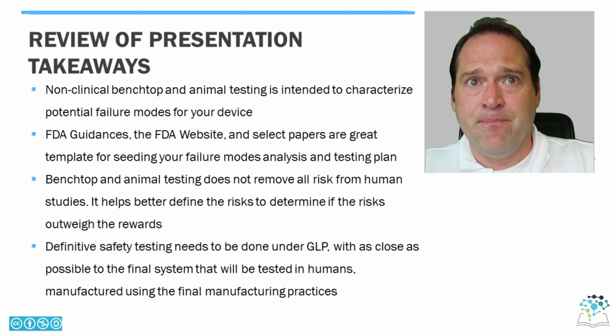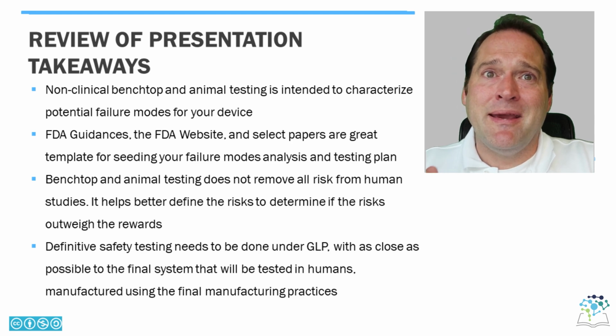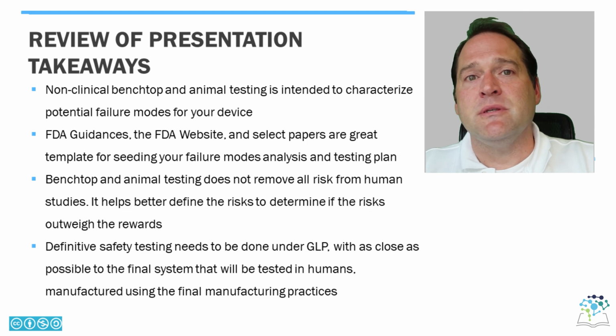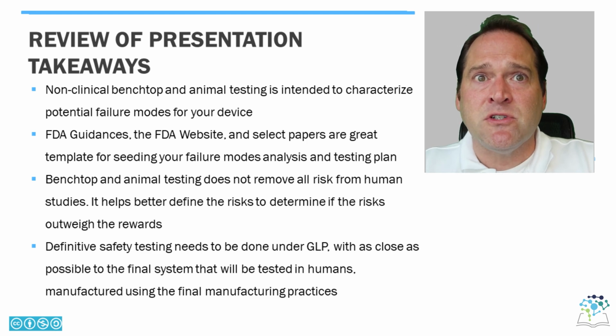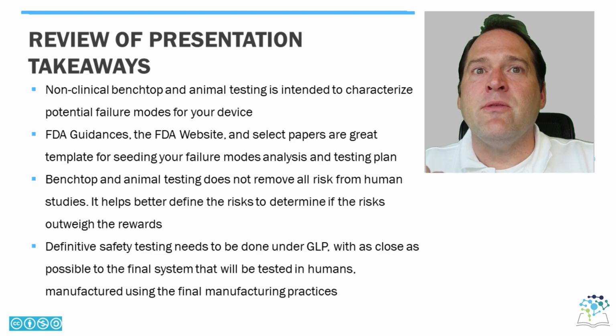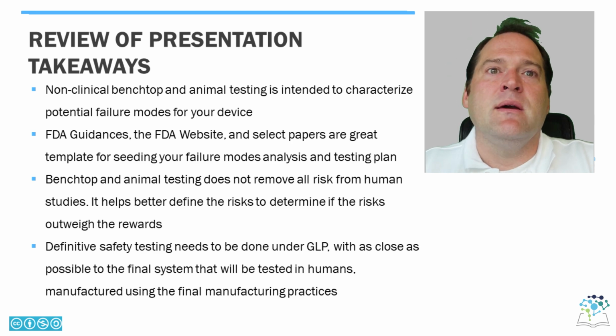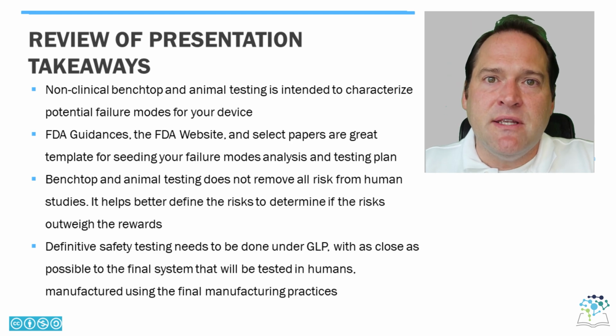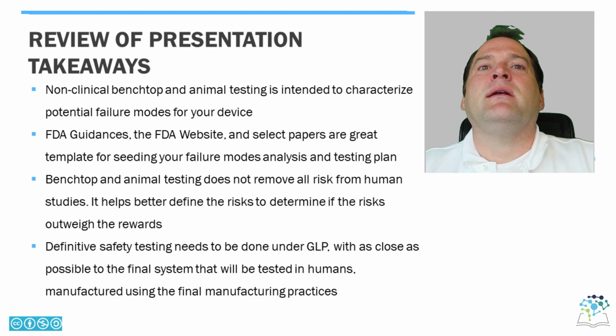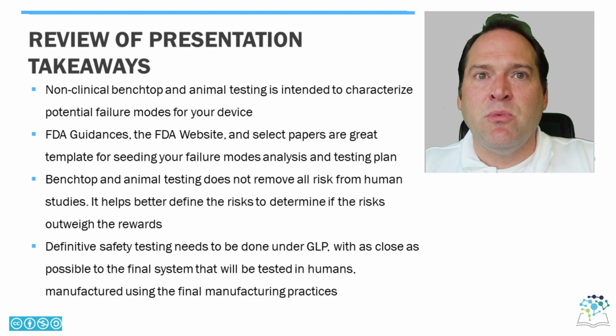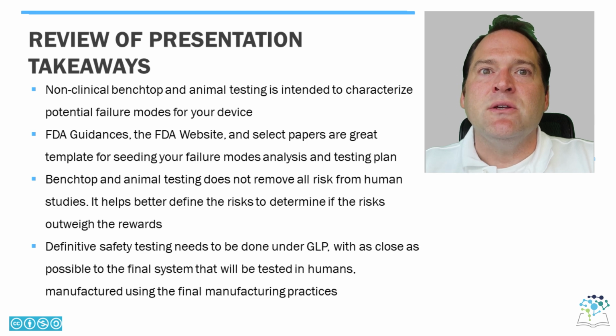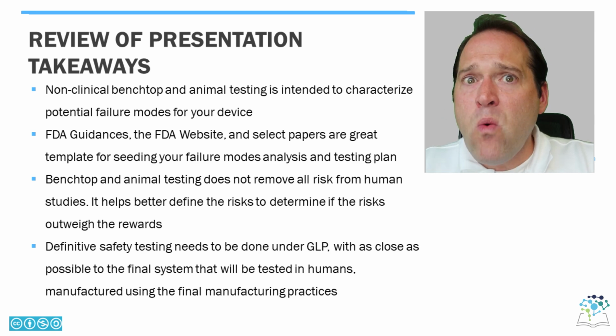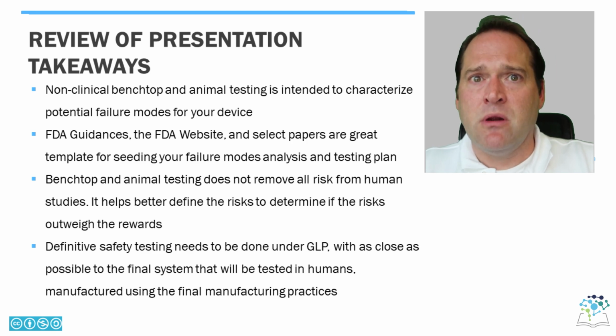2, FDA guidances, the FDA website and select papers are all great templates for seeding your failure modes analysis and subsequent testing plan. 3, benchtop and animal testing does not remove all risk from human studies. It's an impossibility for some devices. It just helps better define the risks to determine if the reward outweighs the risks. And finally, although definitive safety testing needs to be done under GLP, and it needs to be done with as close to as possible the final system that will be tested in humans, manufactured using the final manufacturing practices, not all testing needs to be done in large animals, and you don't always require large animals or a 6-month large animal study.